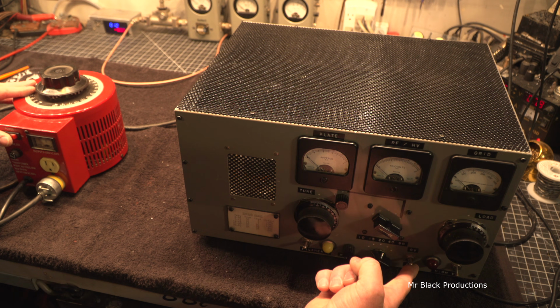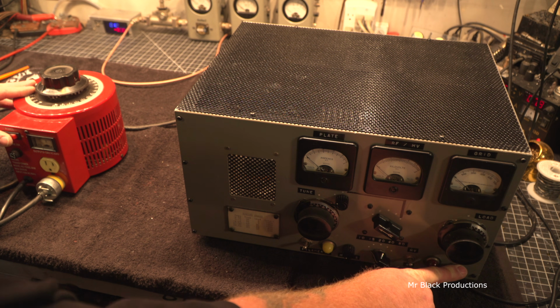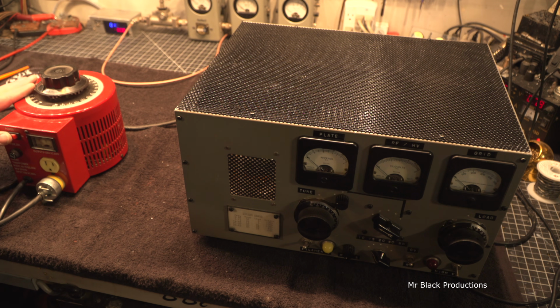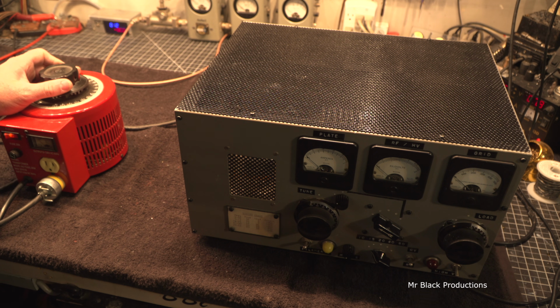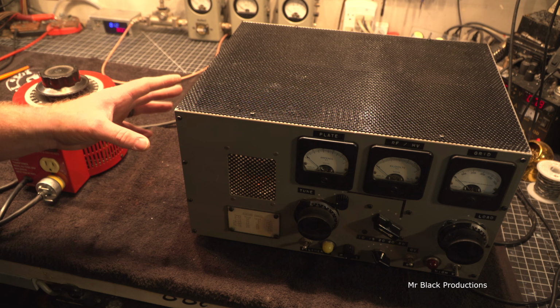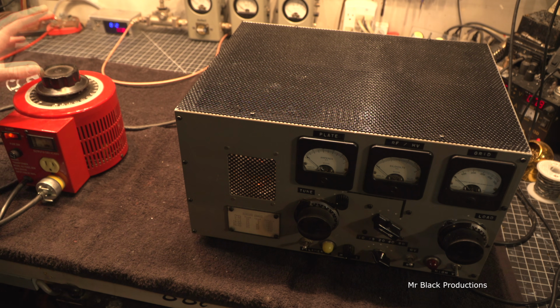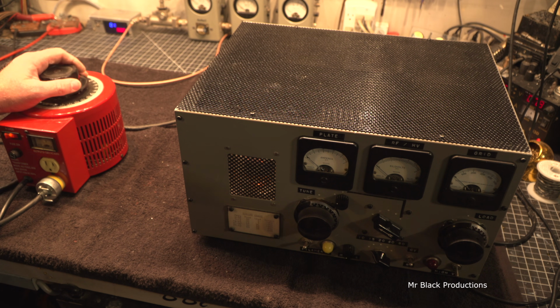Switch is on, high voltage reference is on, even though we have the high voltage neutralized. One hand. We're going to turn on a Variac, and we're going to slowly bring the Variac up. Now the Variac should go incredibly slow and smooth. It should be just as smooth as silk. If there's something inside of here that is shorted out and it's not happy, it's going to represent itself as resistance in this Variac, and you're going to feel it as you're trying to bring it up.